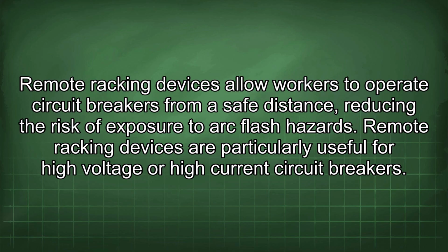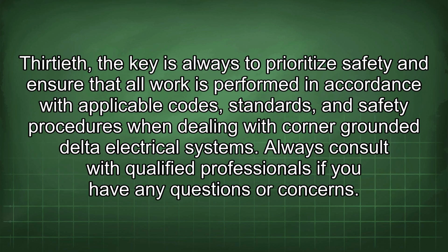Remote racking devices allow workers to operate circuit breakers from a safe distance, reducing the risk of exposure to arc flash hazards. Remote racking devices are particularly useful for high voltage or high current circuit breakers. 30th, the key is always to prioritize safety and ensure that all work is performed in accordance with applicable codes, standards, and safety procedures when dealing with corner-grounded delta electrical systems. Always consult with qualified professionals if you have any questions or concerns.